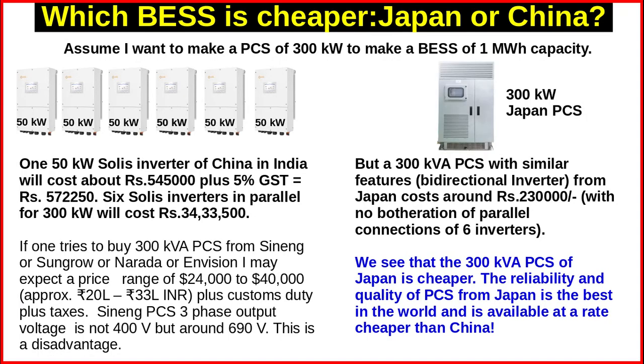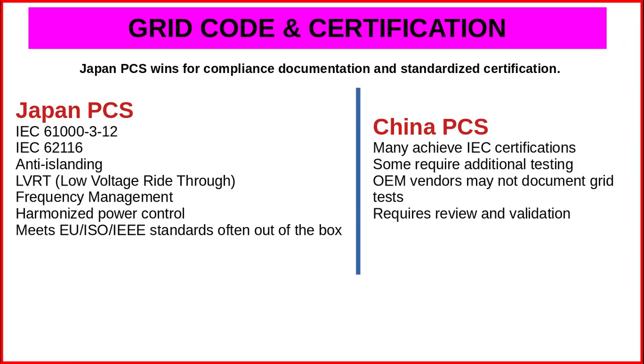Now if I go for a Japanese product, and if I look at the 300 kilowatt option, I can get a PCS from Japan for 23 lakh only, and there is no botheration of parallel connections of 6 inverters. As you know, the Japan brand products are highly reliable, and I was earlier thinking that it will be very costly, but here we see that it is not so. It is in fact cheaper. So we concluded that Japan PCS for a 300 kilowatt system is low cost as well as very reliable. Therefore it is winning over the China PCS.